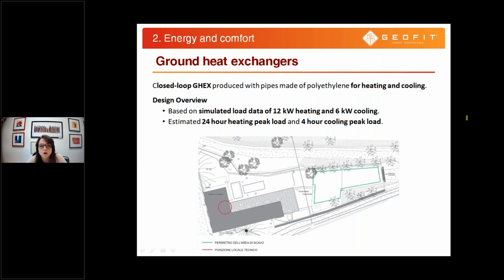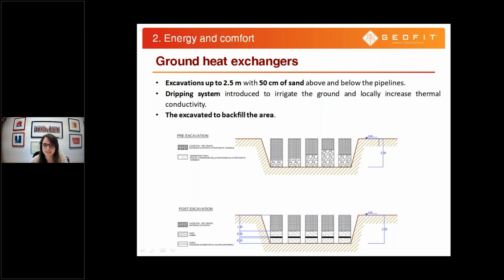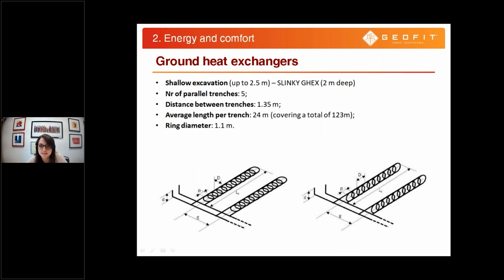To decide the main characteristics of the ground heat exchangers, we ran simulations, defining the heating and cooling thermal loads for our building, and then designed the characteristics of the ground heat exchanger itself. We also designed the kind of excavation and backfilling we were assuming to use, and then went through designing the overall GHEX, which in our case was a special kind: a slinky ground heat exchanger, a superficial heat exchanger that produces coils, as you see here in the slides.